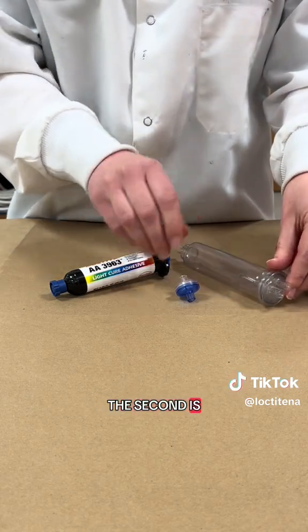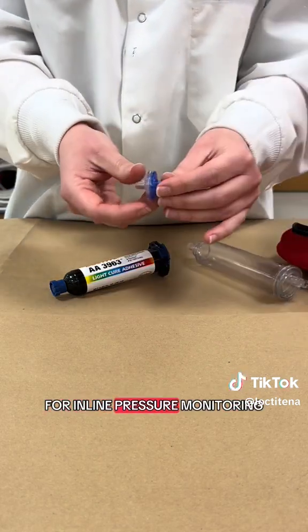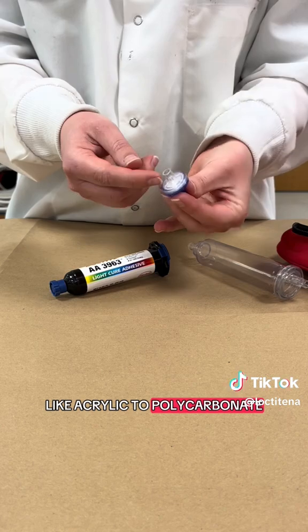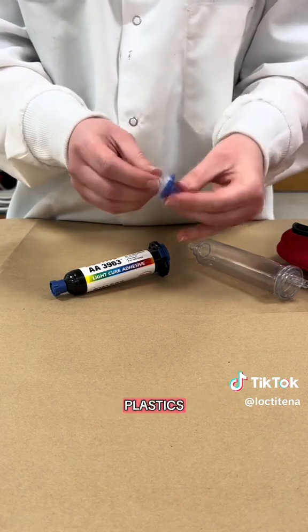The second is a blood transducer for inline pressure monitoring. And this can be made of materials like acrylic to polycarbonate. Again, very rigid plastics.